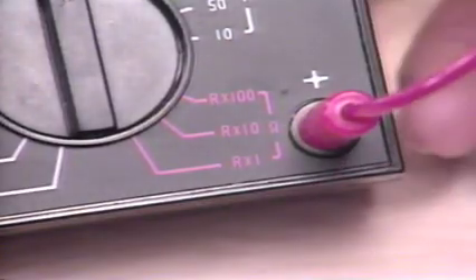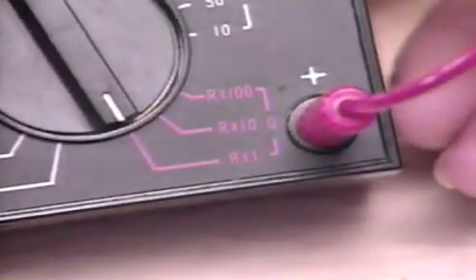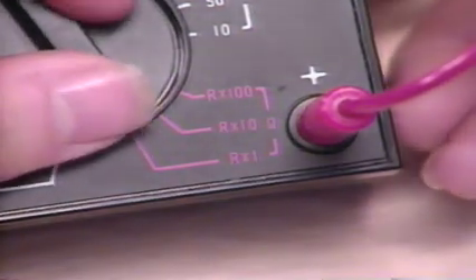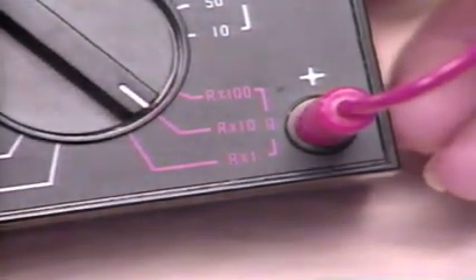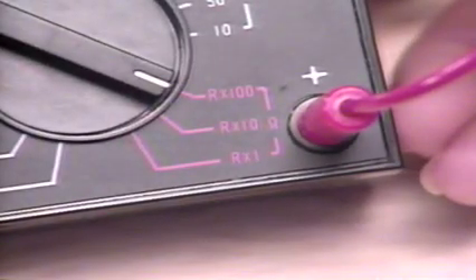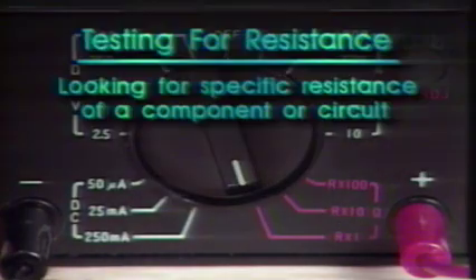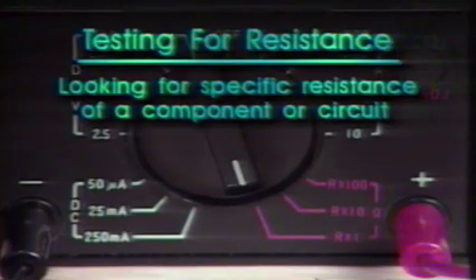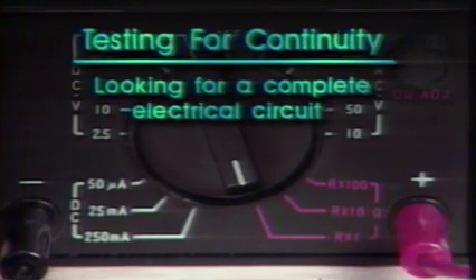When it is positioned here, you are getting a direct 1-to-1 resistance reading of ohms. When the switch is here, the reading is 10 times, and here, 100 times. When testing for resistance, you are looking for the specific resistance of a component or circuit. Therefore, you would probably set the selector on the RX1 setting, since most components and circuits have fairly low resistance. If you are testing for continuity, you are basically looking for a complete electrical circuit, which would equal 0 ohms.